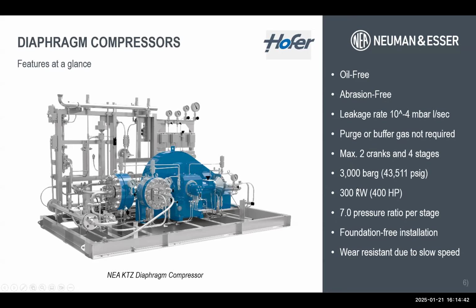One of the nice characteristics of the diaphragm compressor is that they have higher pressure ratios per stage. So for any given application where you need probably 3 or 4 stages on a recip, a diaphragm can do the same work in two, which saves a lot of equipment. They require a bit more maintenance than the recip, so they have shorter uptimes. And that means you have to open up the heads that you see here and replace the diaphragms roughly every 6 months. So it's very common to have spare units on critical services.